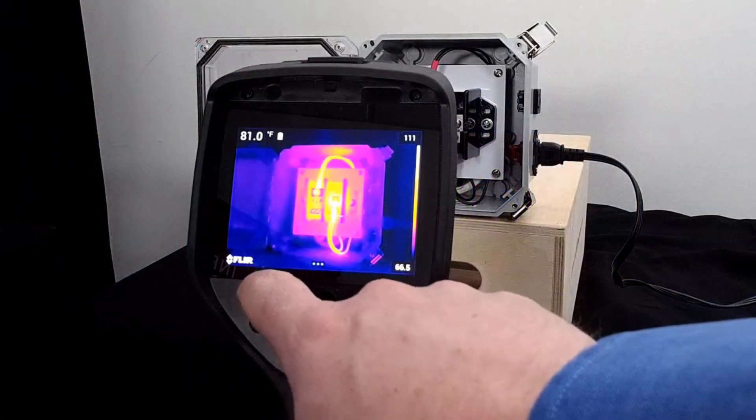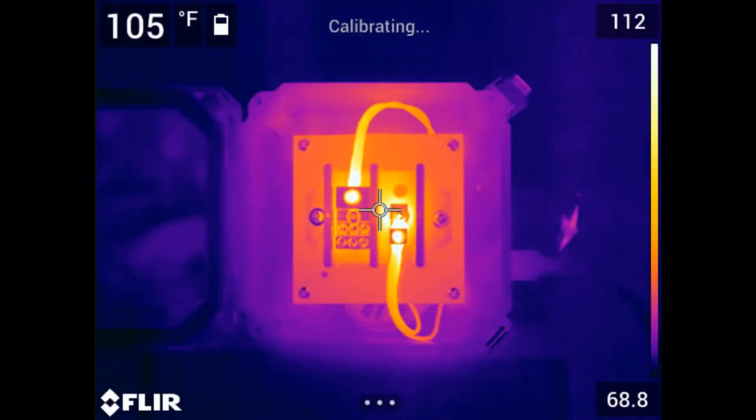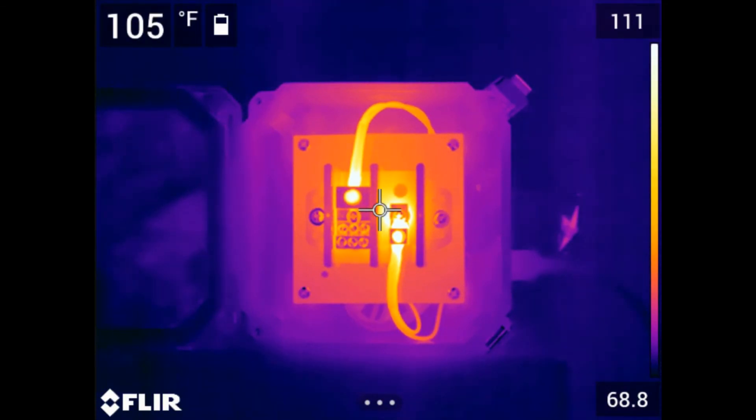Occasionally you'll notice that the live image freezes for a moment. A clicking sound can also be heard during this brief interruption, and the word 'calibrating' will appear at the top of the display. This is normal, and it's called the Non-Uniformity Correction. Thermal energy from the surrounding environment, or that generated inside the camera, can affect the stability of the detector array, impacting the integrity of temperature data and causing areas to appear artificially warmer or cooler. You can force a correction by holding down the image recall button on the back of the camera. The image will pause while a shutter, which acts as a uniform target, drops in front of the array. The detectors will then automatically reset, and the camera will return to live imaging mode.